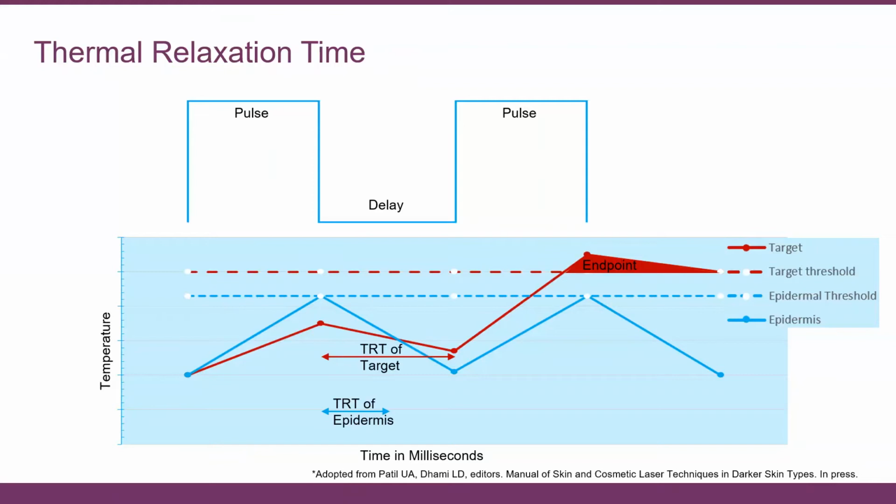And this is basically how a number of different lasers will be used for vascular treatments where they're not necessarily firing a single pulse. You may well find that even though you're only pressing the trigger once, the system could well be firing a multiple number of shots within what we call a pulse chain.